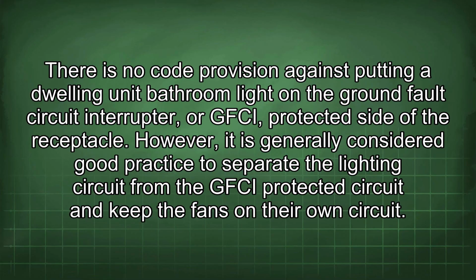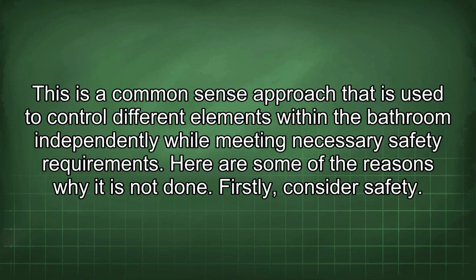There is no code provision against putting a dwelling unit bathroom light on the ground fault circuit interrupter, or GFCI, protected side of the receptacle. However, it is generally considered good practice to separate the lighting circuit from the GFCI protected circuit and keep the fans on their own circuit. This is a common sense approach that is used to control different elements within the bathroom independently while meeting necessary safety requirements. Here are some of the reasons why it is not done.